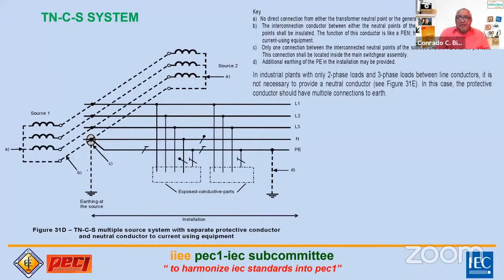So it's very important. The interconnection conductor between either the neutral points of the transformer or the generator star point shall be insulated. So the function of this conductor is like a PEN. However, it shall not be connected to a current using equipment. So ito, only one connection between the interconnected neutral points of the source and the PE shall be provided. This connection shall be located inside the main switchgear assembly. So pwedeng ilagay dun sa loob ng MDB.